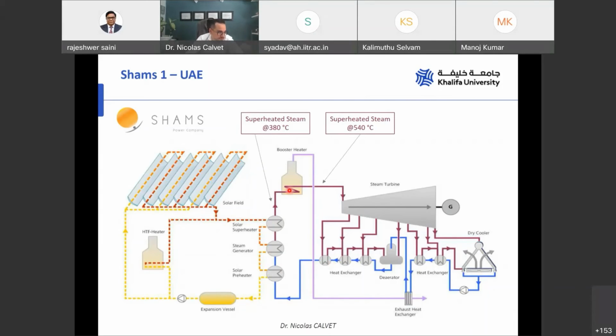So the booster heater is basically used to increase the efficiency of the plant. Why? Because on the left you have the solar field that heats synthetic oil to about 393 degrees. The synthetic oil goes into a heat exchanger to produce the steam for the turbine, and this steam is produced at around 380 degrees Celsius. After that, they burn a little bit of gas to superheat from 380 to 540 C, and this, as you know, increases the efficiency of your power block.